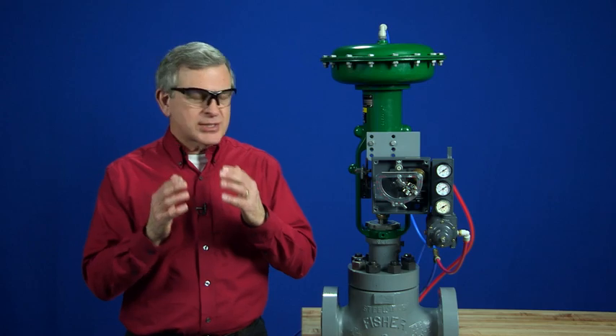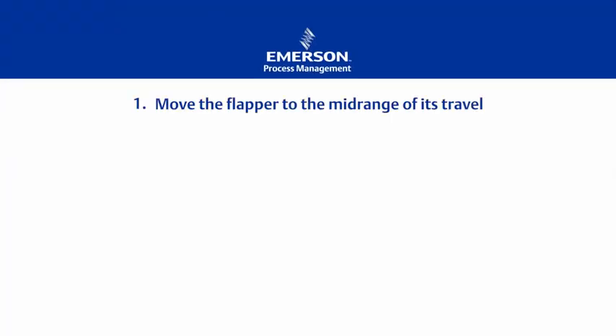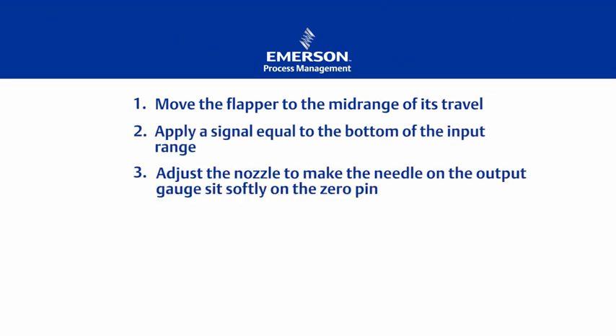We can calibrate the 3582 positioner in just six easy steps. Step one, move the flapper to the midrange of its travel. Step two, apply a signal equal to the bottom of the input range. Step three, adjust the nozzle to make the needle on the output gauge sit softly on the zero pin. Step four, increase the input to find the low saturation point. The output needle should move before the input gets to three and a half.